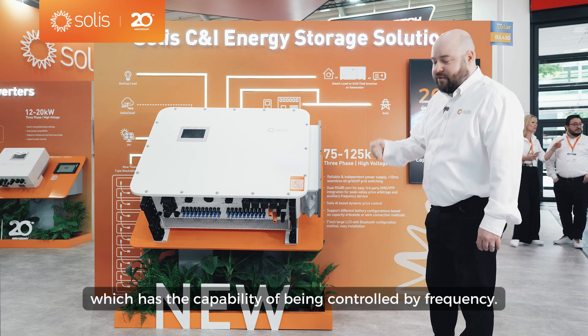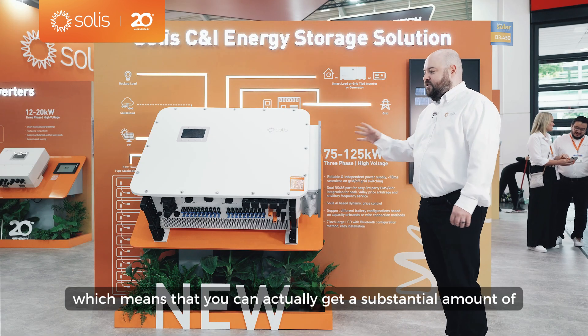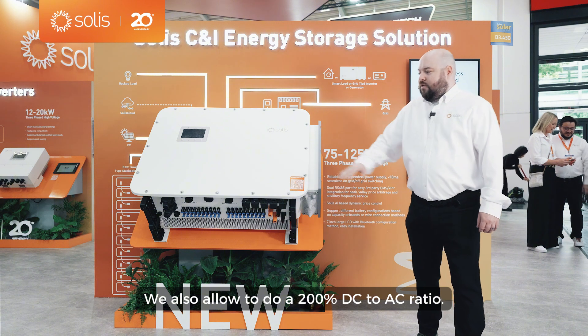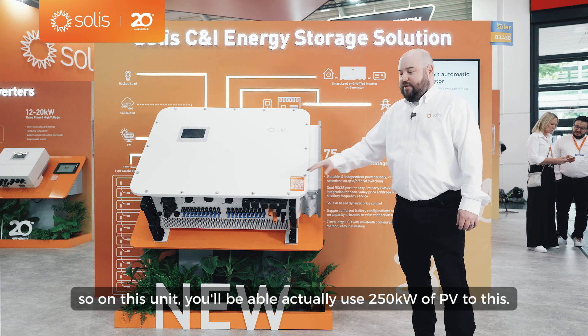This model can be paralleled up to six units, which means you can get a substantial amount of hybrid power on your PV system. We also allow a 200 percent DC to AC ratio, so in this unit you'll be able to use up to 250 kilowatts of PV.